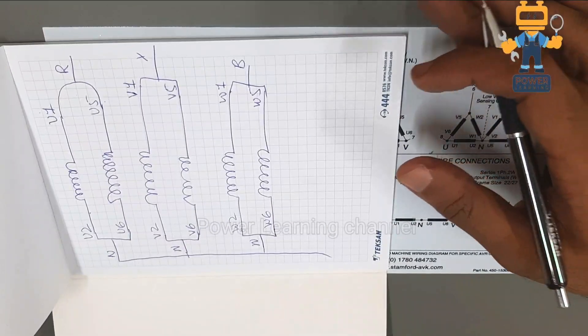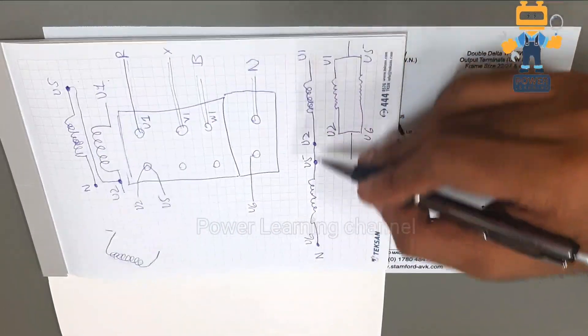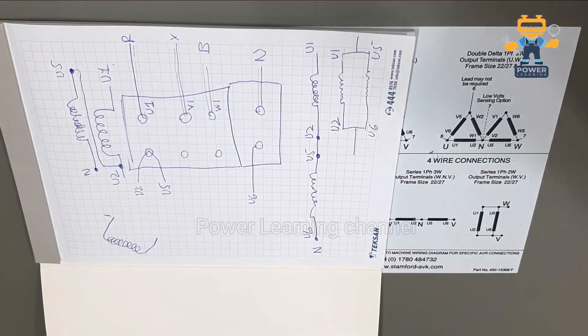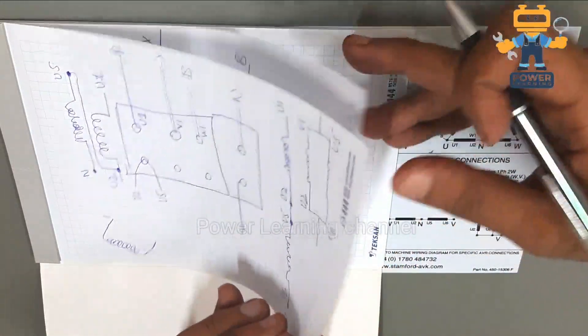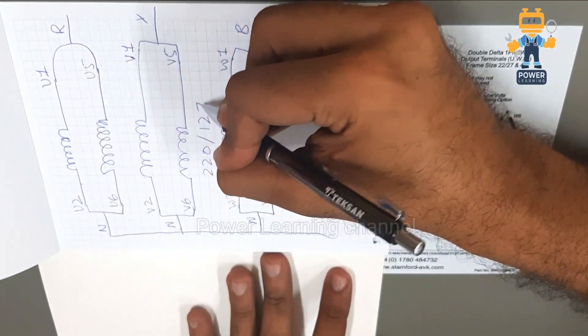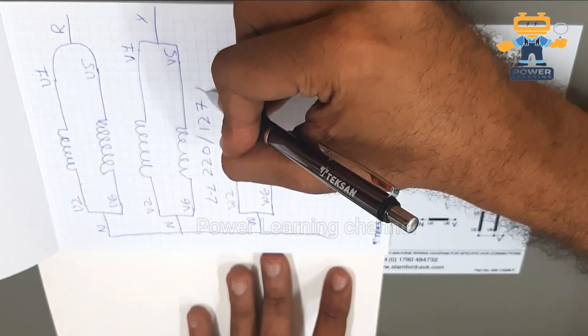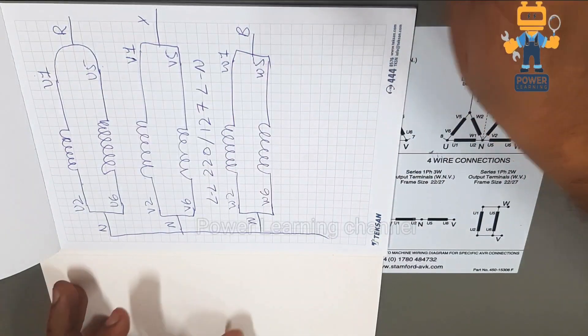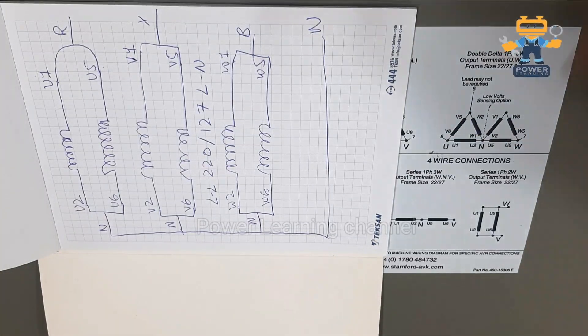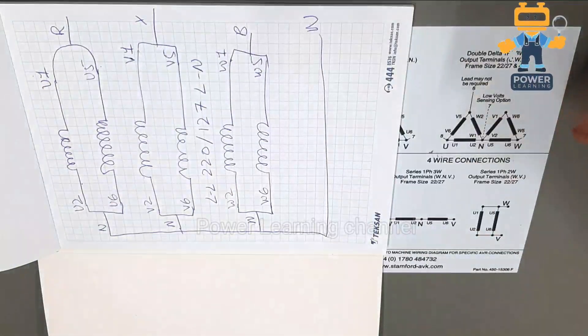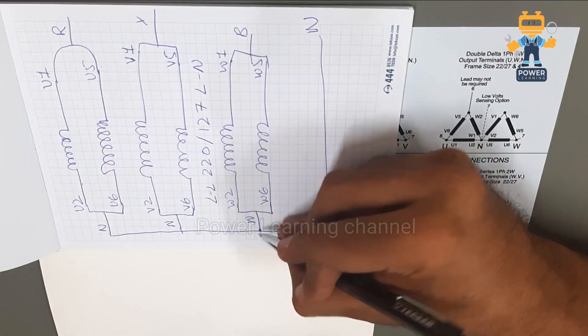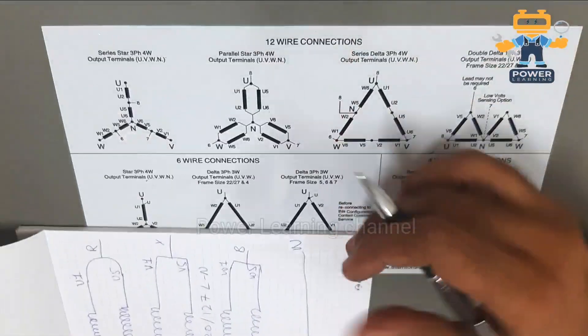With parallel star configuration you get 220 volts line to line and 127 volts line to neutral. All three neutral ends are connected at one common point. Four wires go to the breaker — three phase wires and one common neutral wire taken from that single star point.